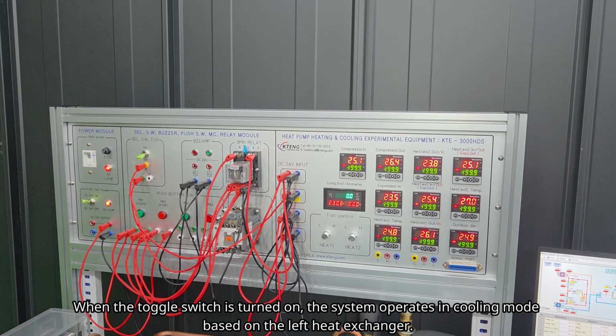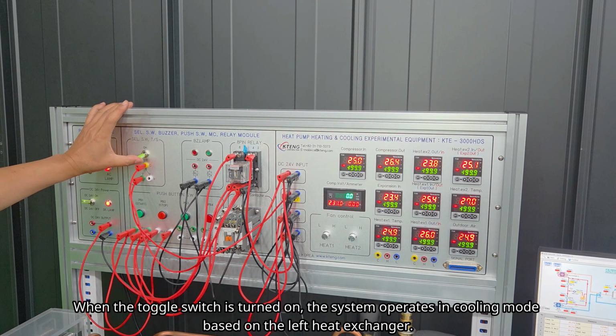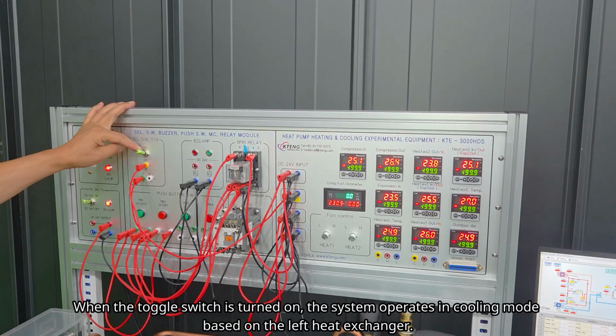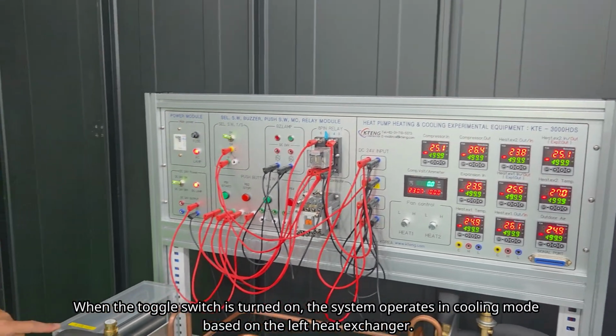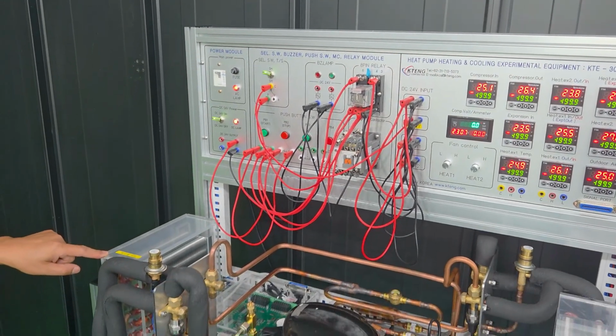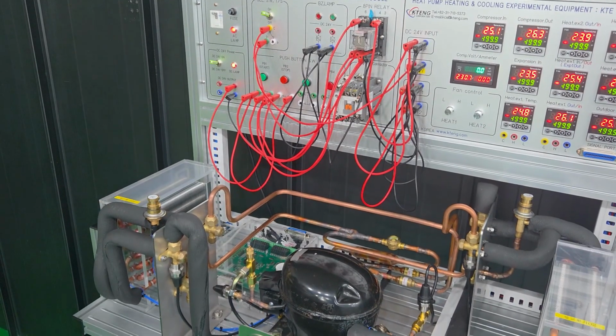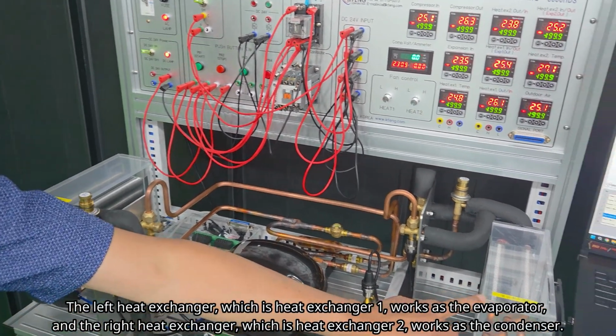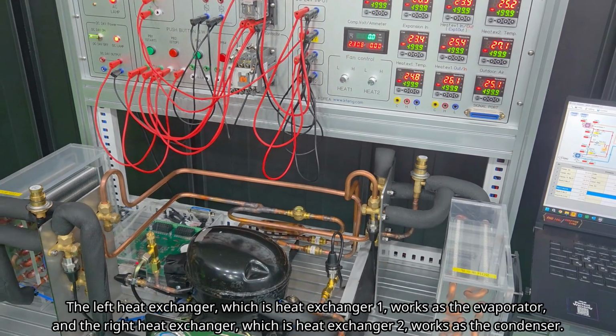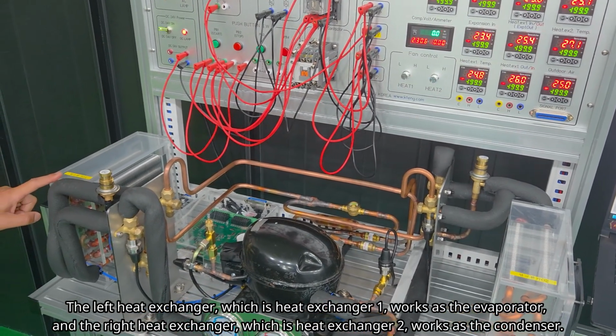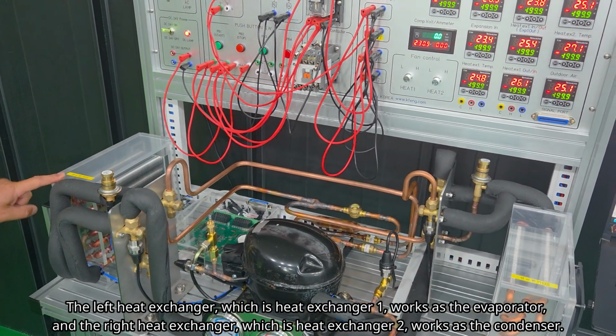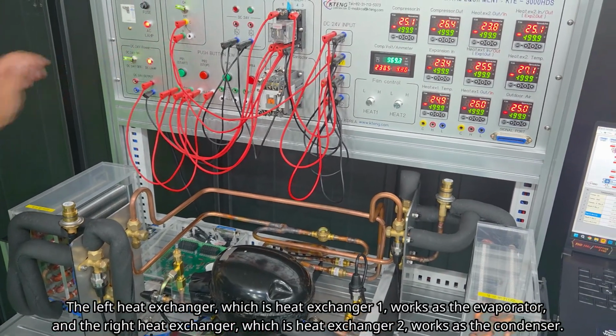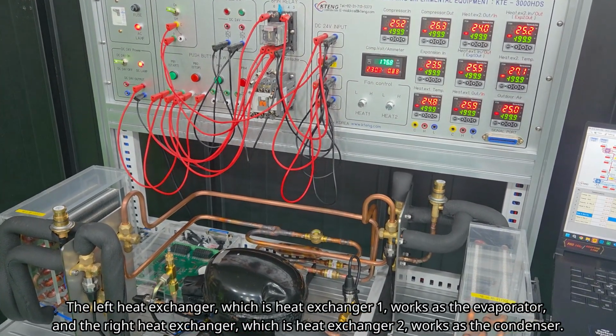When the toggle switch is turned on, the system operates in cooling mode based on the left heat exchanger. The left heat exchanger, which is heat exchanger 1, works as the evaporator, and the right heat exchanger, which is heat exchanger 2, works as the condenser.